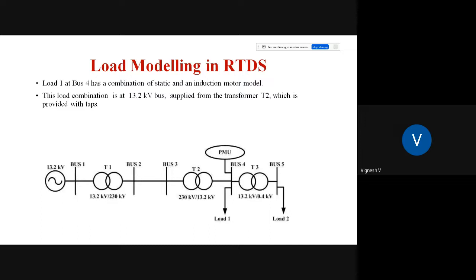So now let's see how exactly we use this load modeling in RTDS. This is one system. RTDS is a real-time digital simulator that we had, which can simulate things in real time, near real time. This is one synthetic power system that we developed in the RTDS, and we put a PMU at bus number 4. This PMU could be a software PMU which is inside the RTDS, or it could even be a hardware PMU. We used both hardware and software PMUs. And to create a disturbance, since without disturbance we cannot model the load in the measurement-based approach, the transformer T2 had taps, and you could change the taps to get step changes in the voltages. Next slide, please.